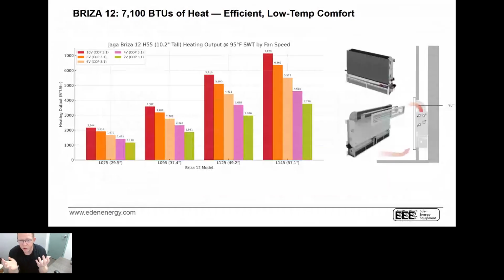The obvious question that comes from people is, well, how many BTUs can I get doing this? Well, the reality is you can get up to 7,200 BTUs utilizing this unit. More importantly, you can get as little as 1,100 BTUs out of the unit. And this is a photo of a typical convector on the right-hand side. It's designed to be recessed into the wall, recessed into the ceiling.